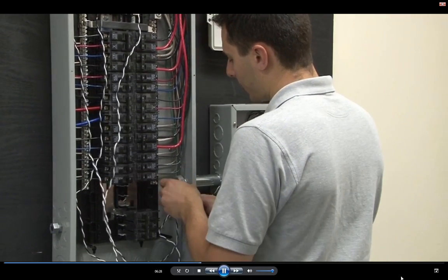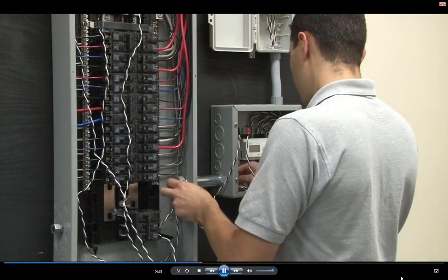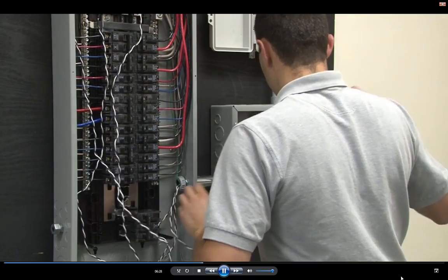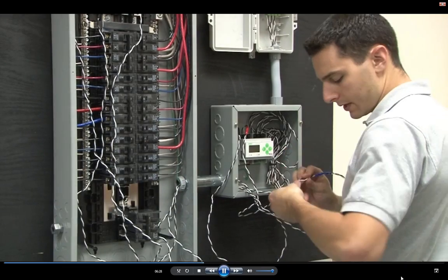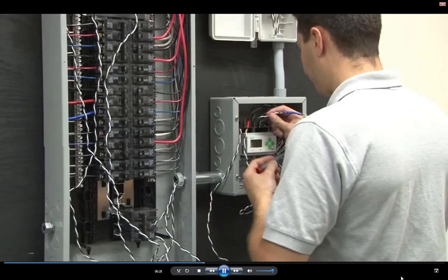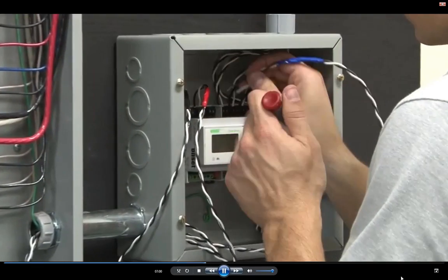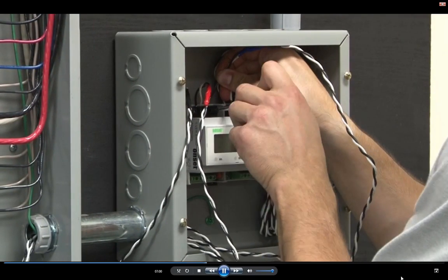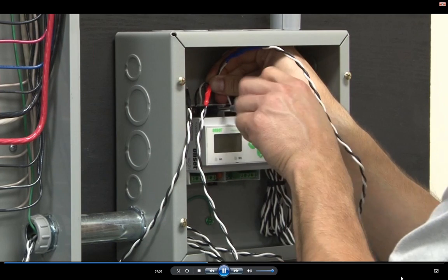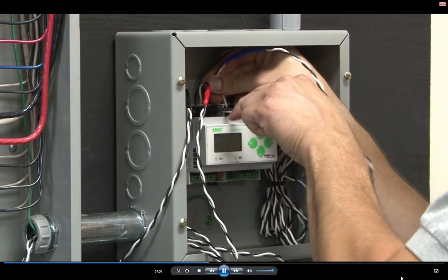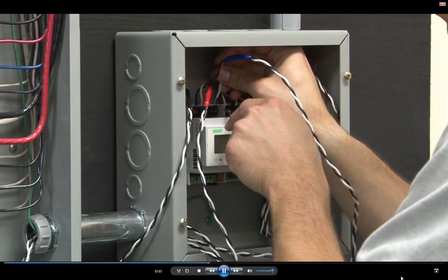We'll run our final CT conductor through the conduit to the phase C terminal of the E50B2. The black conductor once again will be connected to the negative terminal, and the white conductor will be connected to the positive terminal.